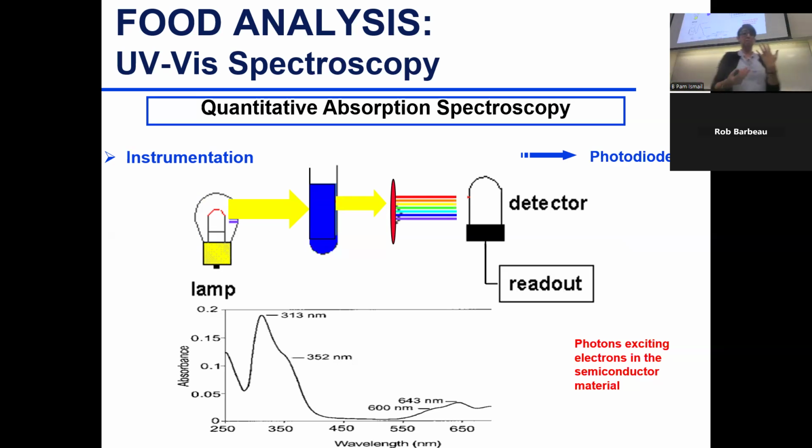So at this point, when the light that is transmitted reaches an array of diodes, that's why it's called photodiode array detector. So it reaches an array of diodes, a lot of diodes.